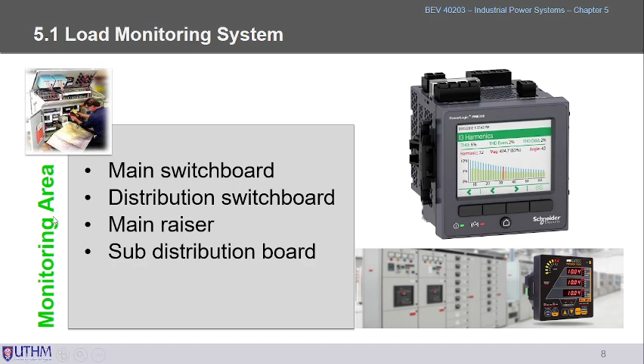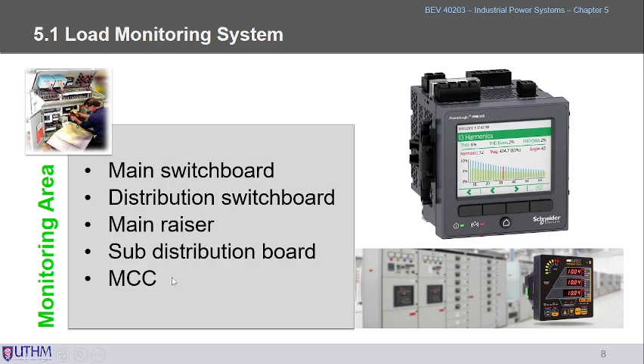And of course we cannot avoid monitoring our MCC, motor control center. So at the MCC you can monitor not only the voltage and the currents, but the frequency is also very important, because the frequency is related to the timer. The timer depends on the frequency operations. So if our frequency is deviated, then the timer that controls the PLC, for example, will also be disturbed.